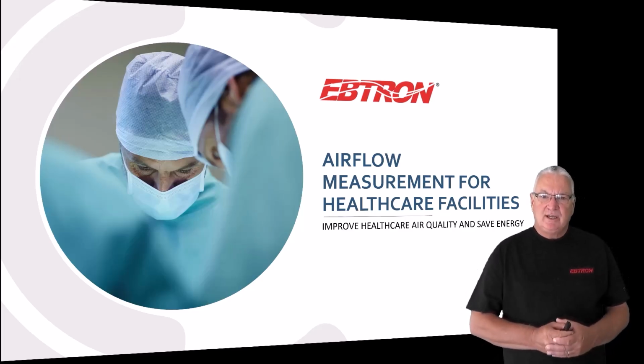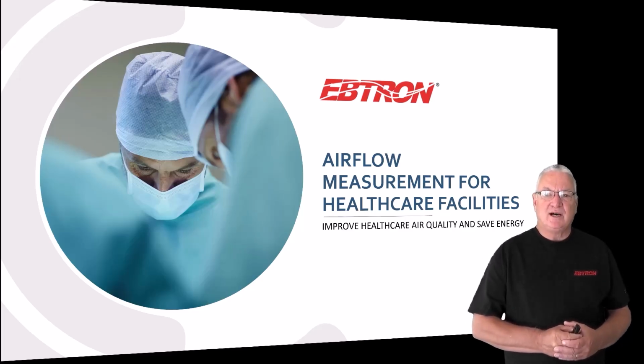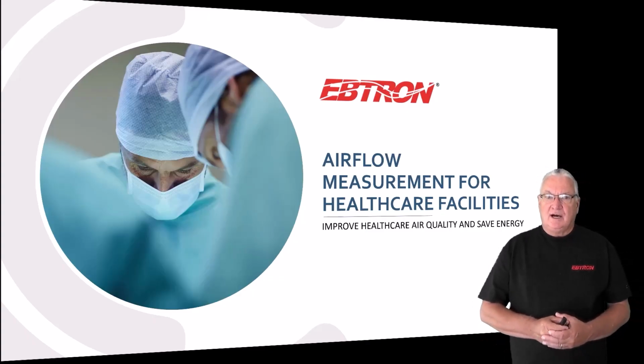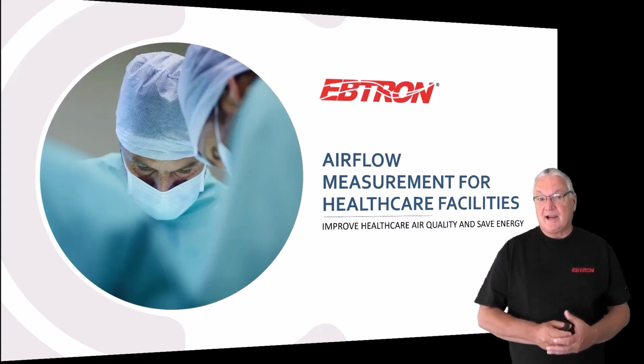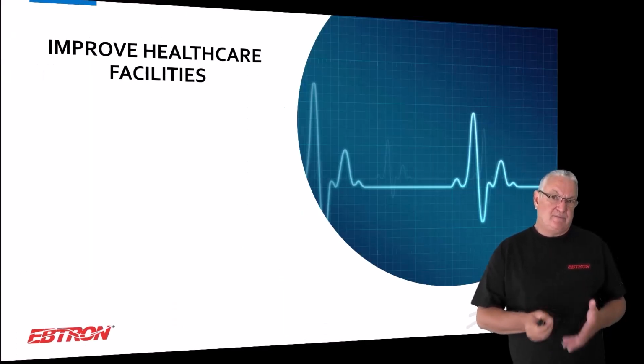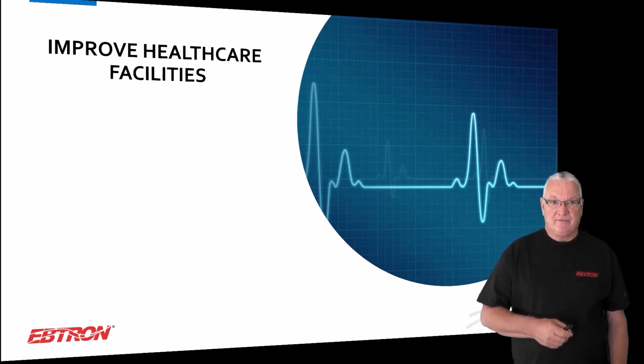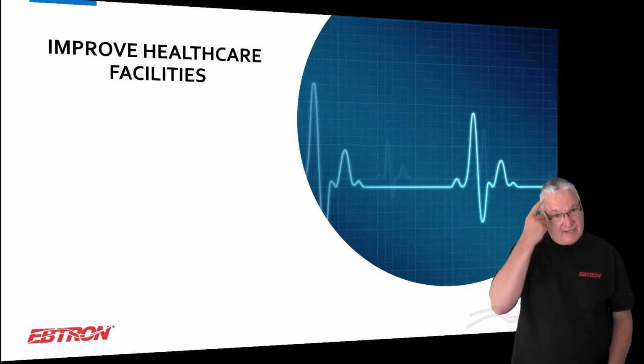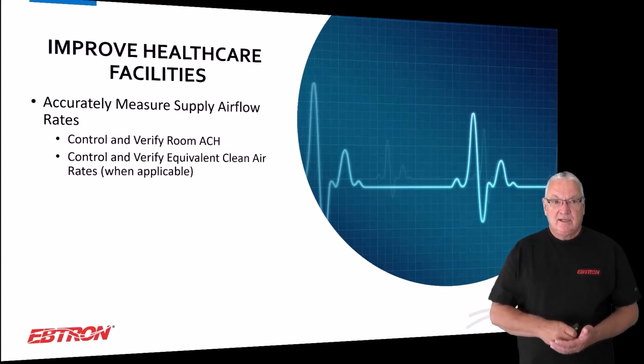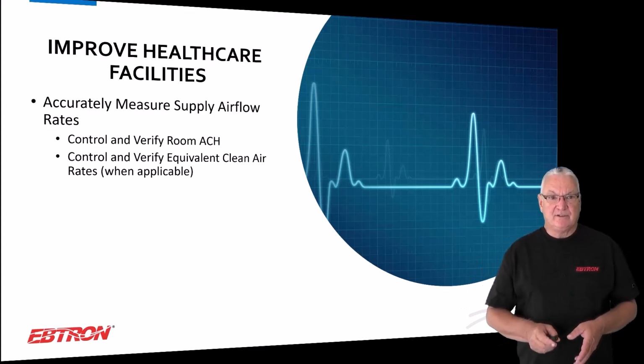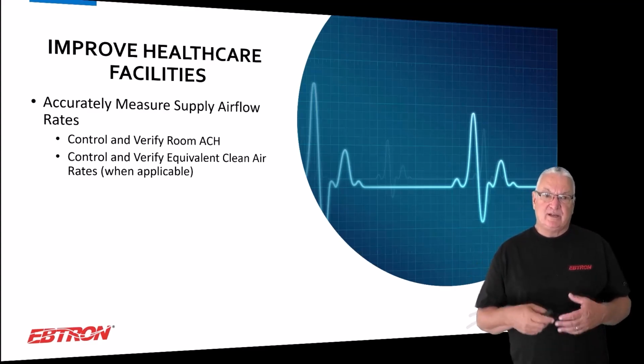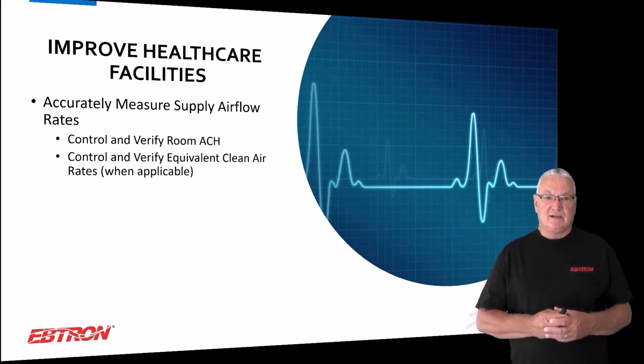Today I'm going to give you a presentation on airflow measurement for healthcare facilities, with the idea of primarily improving healthcare air quality, but also saving some energy by doing things properly. When it comes to healthcare facilities, I'm going to be pretty blunt on a few things I say today. I hope it doesn't offend anybody. But basically, when it comes to improving healthcare facilities, we really need to make sure that we have accurately measured the supply airflow rates. The reason we need to do that is we need to control and verify room air changes per hour. That's going to be very important. There may be other reasons why you want to do it, but that is a very important reason.